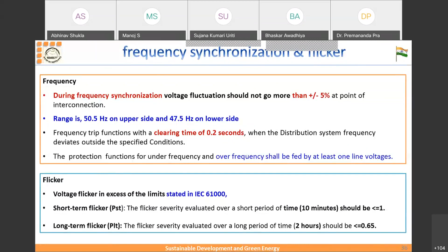Flicker, IEC 61000, I think you all are aware of what flicker is. If there is flicker, the power quality will reduce. Harmonics should not go beyond 5%. So the maximum total harmonic distortion current is less than or equal to 5%, and not more than 50% of the rated inverter output. So this is something challenging.